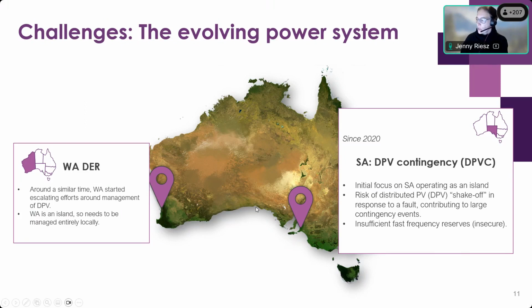In that case, we need to manage the possibility that a large amount of rooftop PV can shake off, or disconnect, in response to a fault, which can then contribute to a large contingency event. And I'll talk a little bit more about that in a minute. So the big challenge there was around managing the availability of frequency reserves, particularly fast frequency reserves, given that we would expect to have very low inertia on the grid at these times as well. So very much relying on resources that can deliver very fast frequency response, such as batteries.